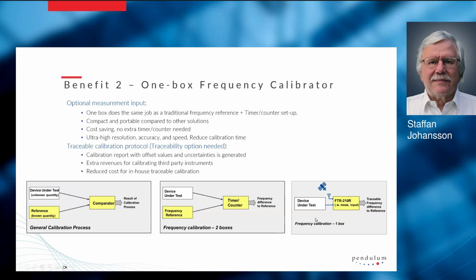When you use the measurement input in the FTR-210R, you have everything in one place. You have one box containing both the reference and the timer counter. All you need is a GNSS antenna. So you connect the device under test and you get your traceable frequency difference to the reference. And there is no manual offline calculation; the data and the uncertainty are done automatically inside the box. So you save a bit of time there. So there's an obvious cost saving. You don't need any extra timer counter to do this calibration.